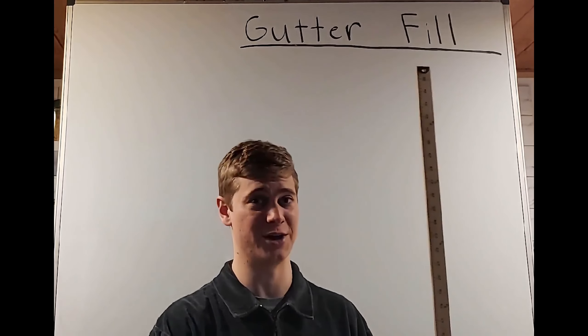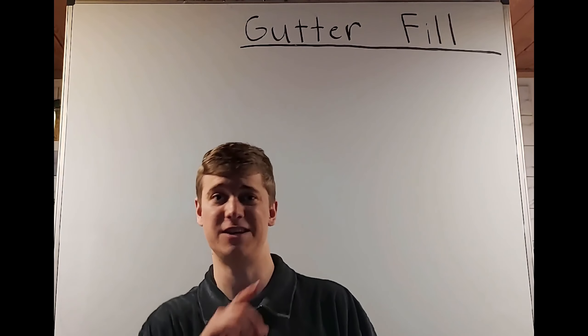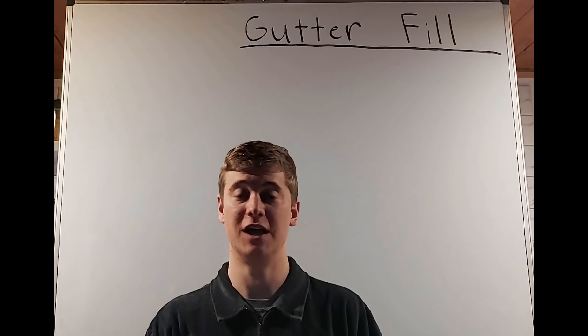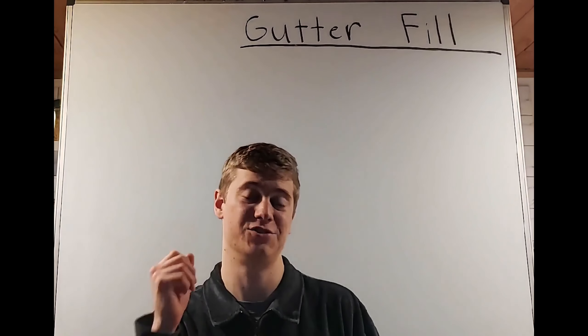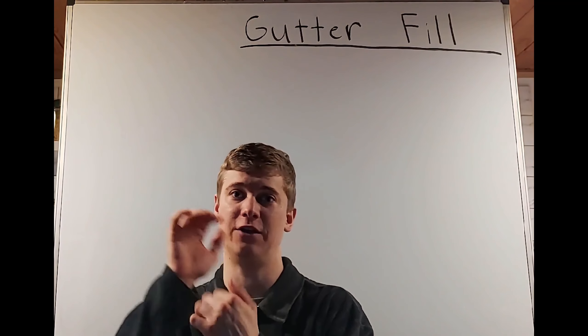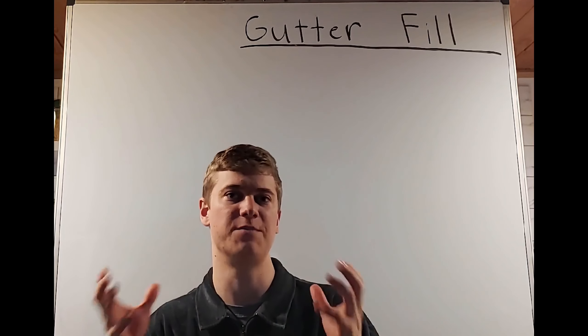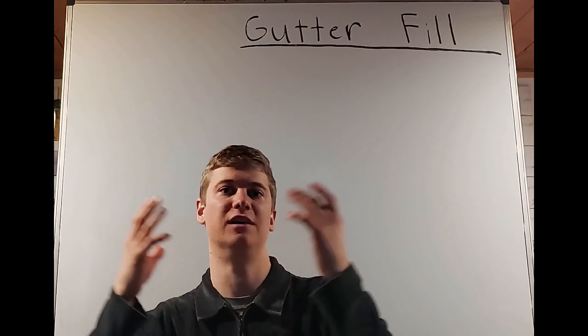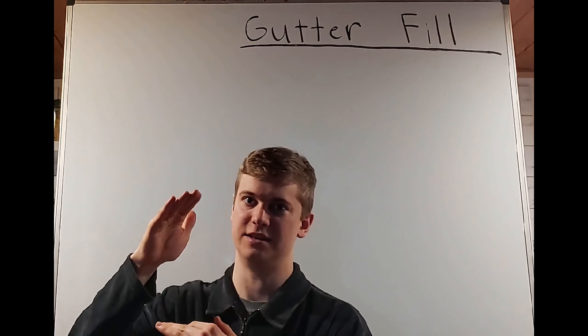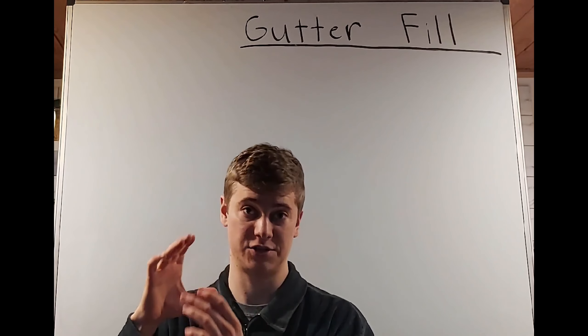Welcome to this video all about gutter fill. The first rule we need to know about gutter fill is the cross-sectional area shall not exceed 20% of the cross-sectional area of the box. When we're thinking about the cross-sectional area of a box, we're not thinking about volume. Something is missing, and that would be the length. We're just talking about the depth and the height, which gives us that cross-sectional area.